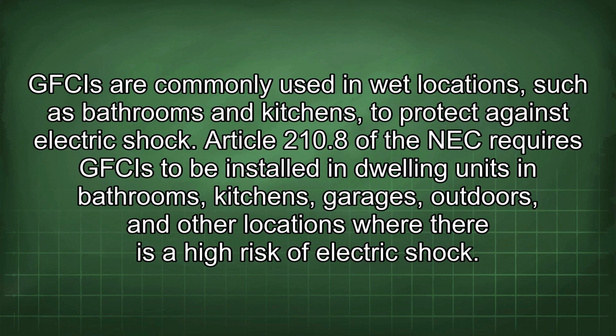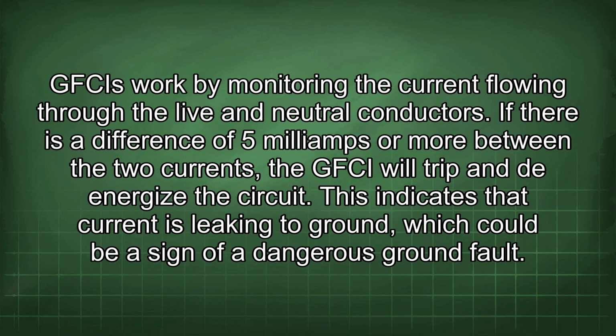GFCIs are commonly used in wet locations, such as bathrooms and kitchens, to protect against electric shock. Article 210.8 of the NEC requires GFCIs to be installed in dwelling units in bathrooms, kitchens, garages, outdoors, and other locations where there is a high risk of electric shock. GFCIs work by monitoring the current flowing through the live and neutral conductors. If there is a difference of 5 mA or more between the two currents, the GFCI will trip and de-energize the circuit. This indicates that current is leaking to ground, which could be a sign of a dangerous ground fault.